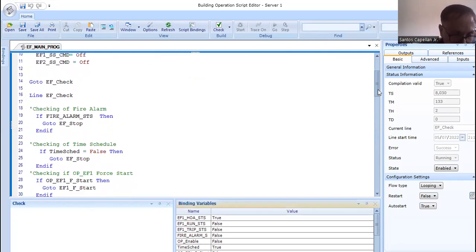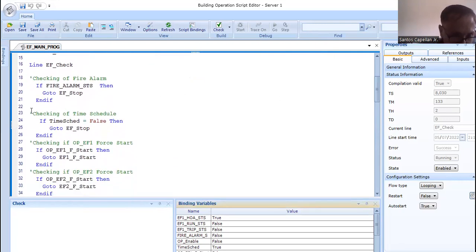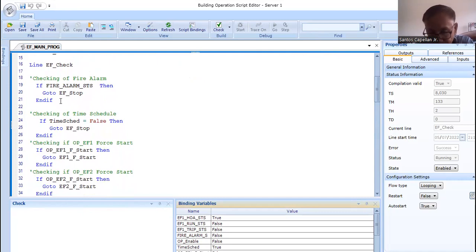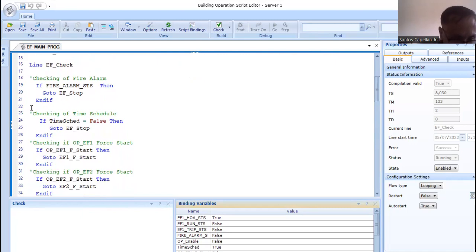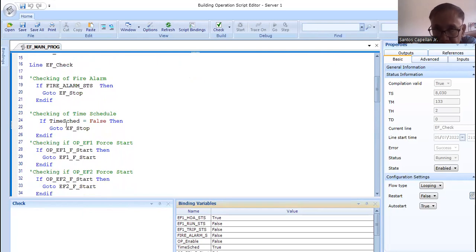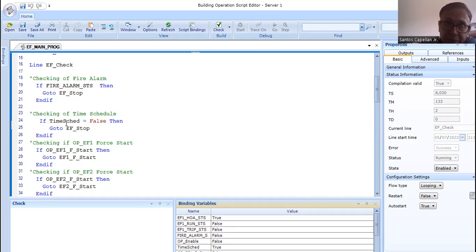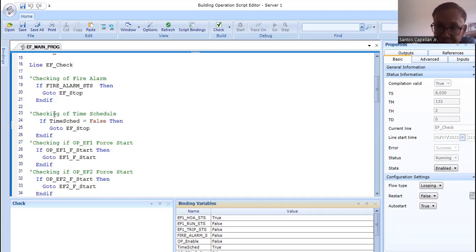If there is no fire, the program goes down line by line. At line 22-23 it checks the time schedule. The time schedule controls when the fans run, because there may be periods — like 12 to 5 a.m. — where you can turn off the exhaust fans to conserve energy, implementing green building practices.